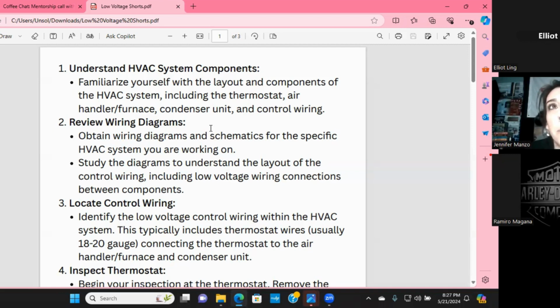So we tend to believe that the problem is always in the control wiring because that's what's field wired. That's what we wired or the installing technician wired. That's not always the case. I have seen many, many times, like in mouse situations where a mouse gets in there and chews the factory wiring. We may think we know what the factory did, but we like to go by color. Our brains form patterns. And sometimes we will go by color and think this one's blue or gray or brown. This must be common, when really it's a live wire and you could get hurt, A, or you could further short the system. It's 24 volts, not gonna hurt you too bad, but you never know what a mouse could chew.